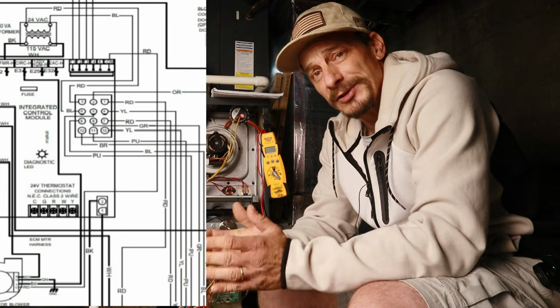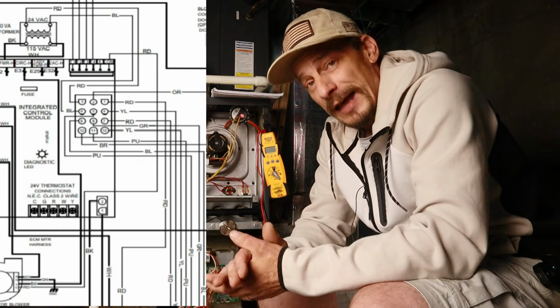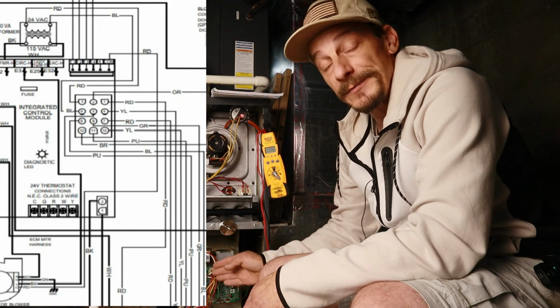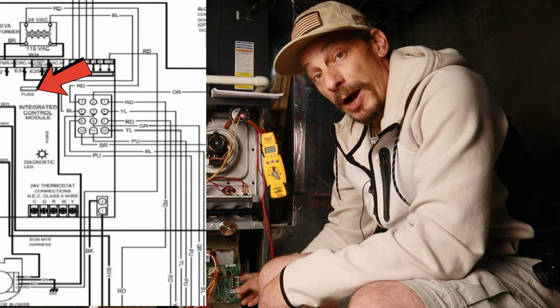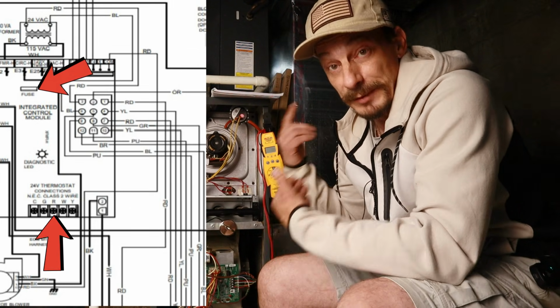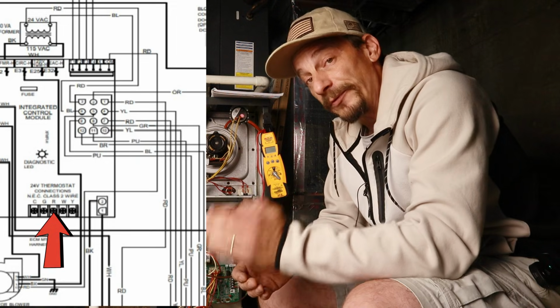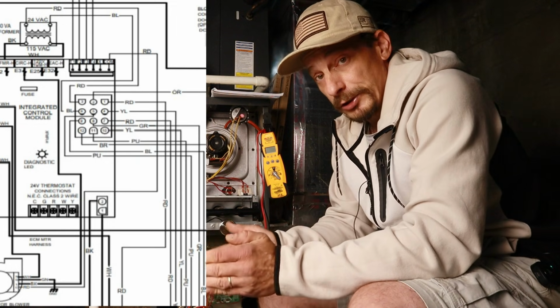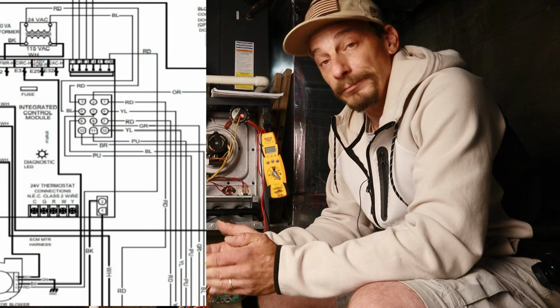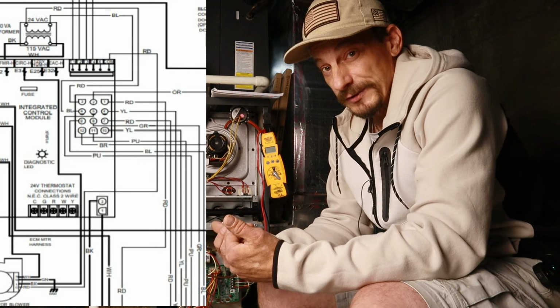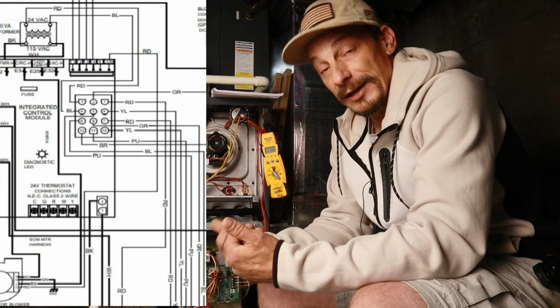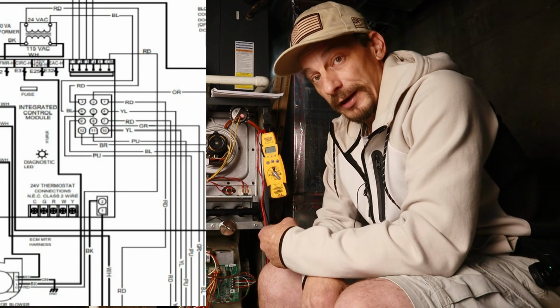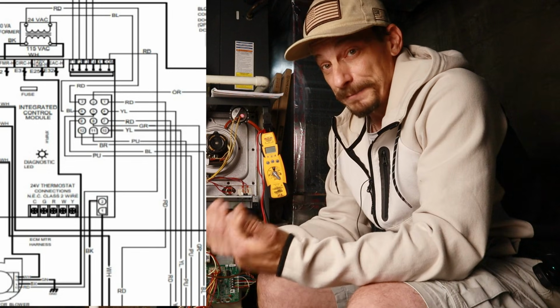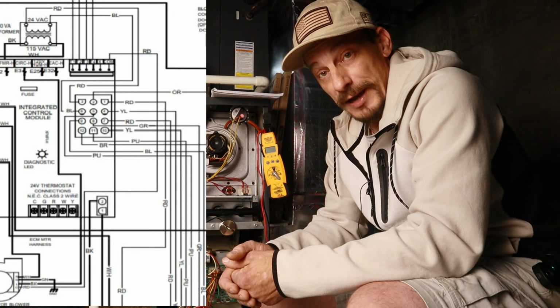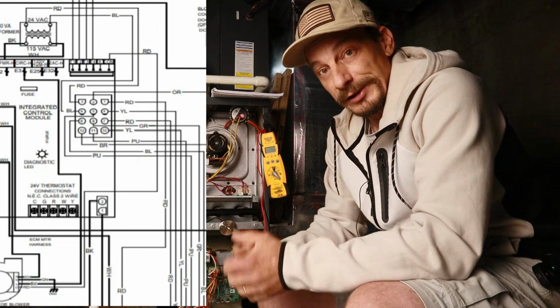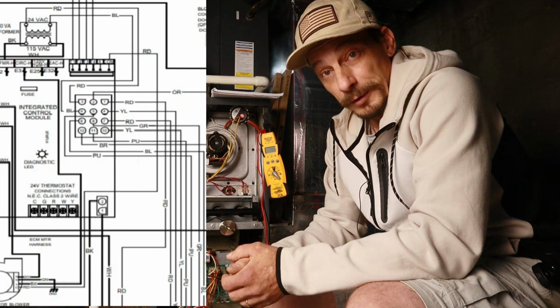Now here's another thing a lot of schematics may or may not show you, and that is once the 24 volts leaves the fuse, it's going to ultimately end up on the R terminal, on our terminal blocks that ultimately goes up to our thermostat. But between the fuse and the R terminal, it is usually going to go through a safety of some kind. Now, different brands and different models might go through different types of safeties, but there's always going to be some kind of safety that 24 volts gets to before it goes to that R terminal. And once again, sometimes a schematic may not show you this. We don't see it on the schematic we're looking at today, but you can pretty much guarantee every furnace is going to work that way.